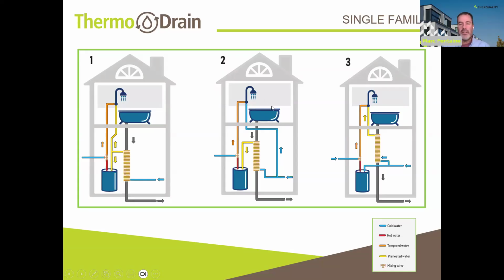We see number 2 as being the installation of choice. Most of the installations are done this way, but number 3 is a good way to do it if the plumbing lines are far away or the bathroom is far away from the water heater. In some cases where we're looking to maximize efficiency, number 1 here is where we would be able to get another roughly 10% boost in efficiency. So the preheated water coming out of the thermodrain would feed both the hot water side of the water heater and the cold side of the shower fixture. This is kind of dependent on what you're trying to do, but I would say keep in mind that usually number 2 is where we run across the most, and would be a good way to do the installation.